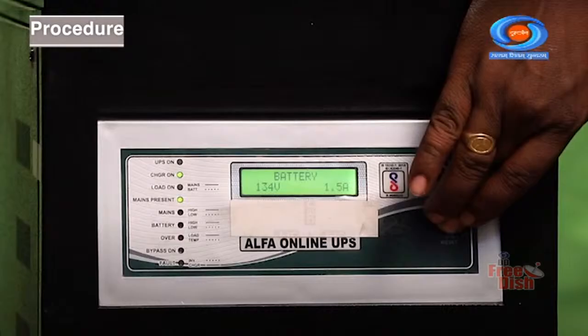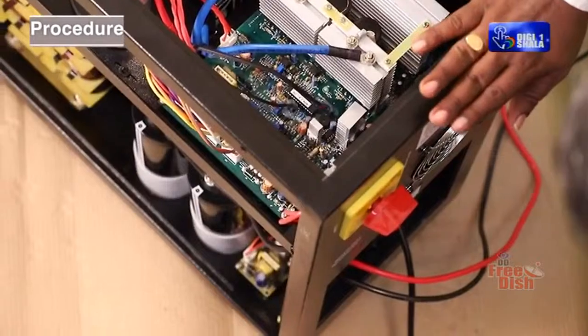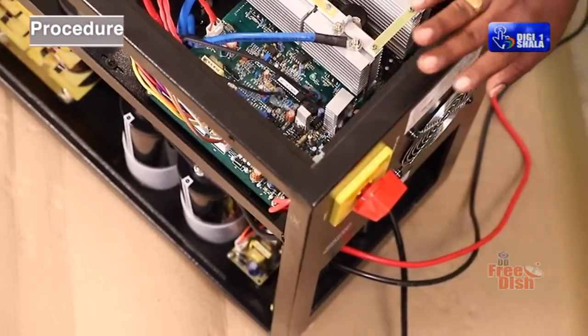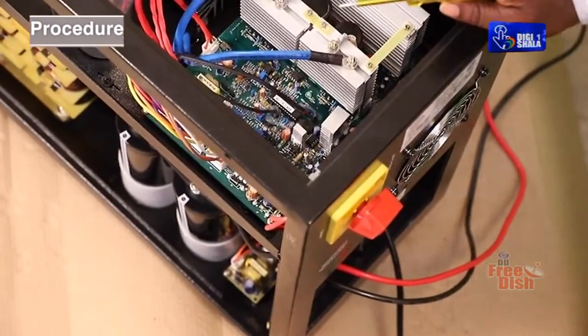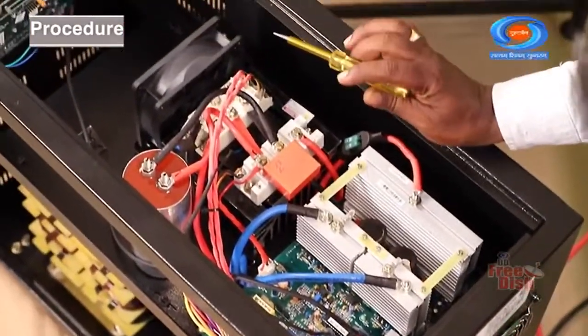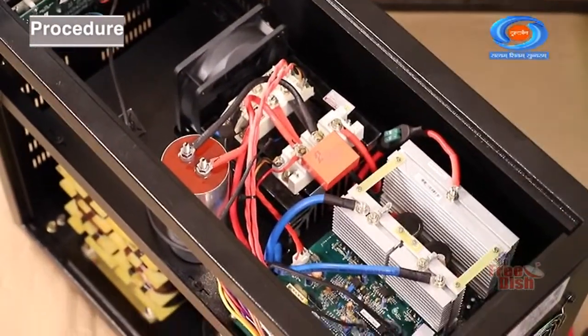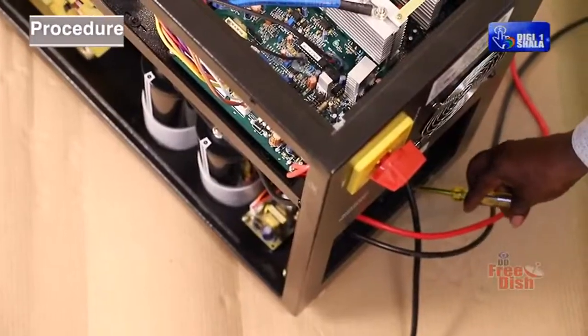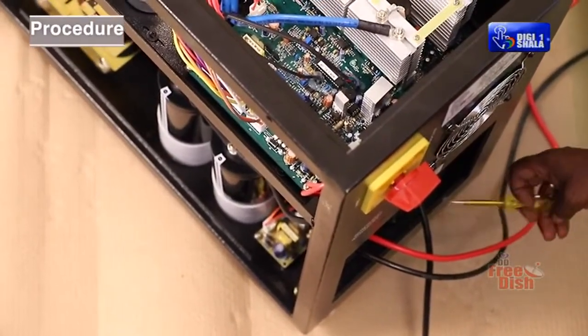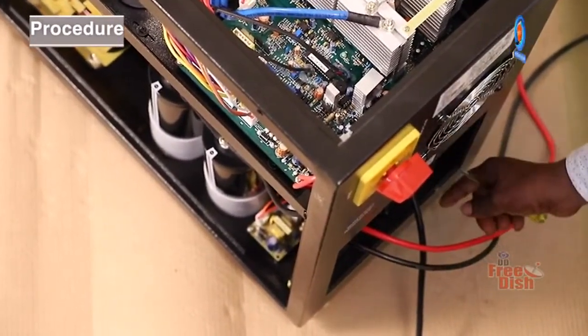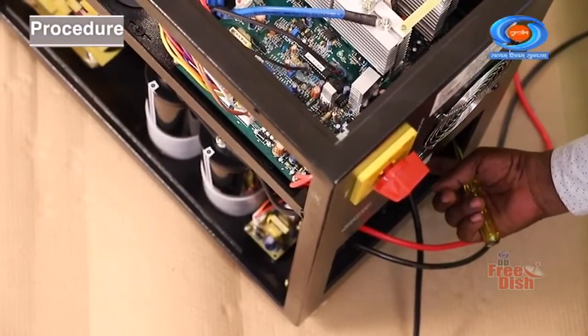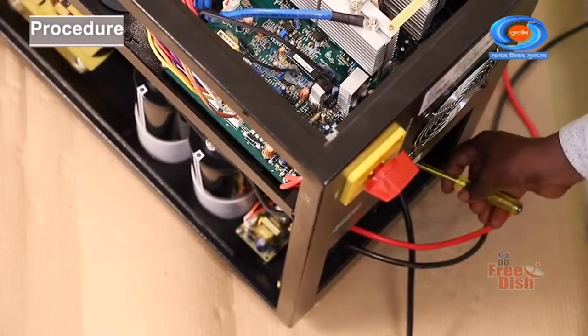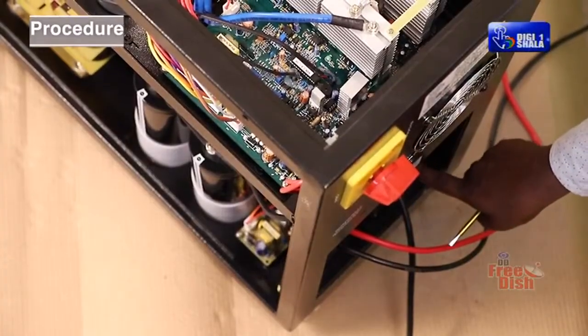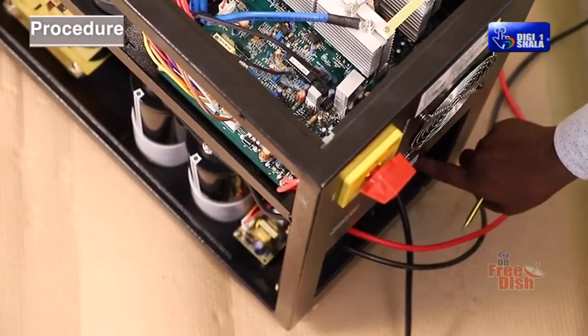Check the backup LED yellow. If the yellow backup LED lights off, the UPS and battery are in the off position. If the backup LED is not off, it indicates the UPS is always in battery mode. The causes for this fault may be in the power cord, fuse, or abnormal voltage.